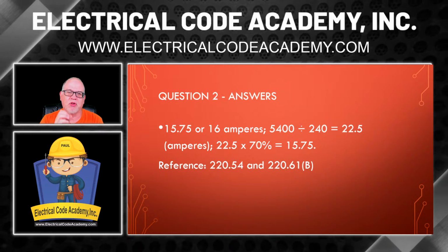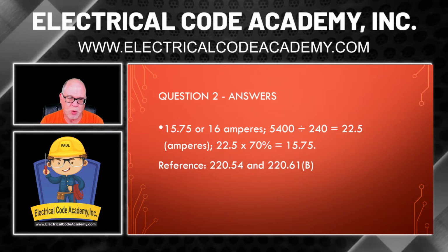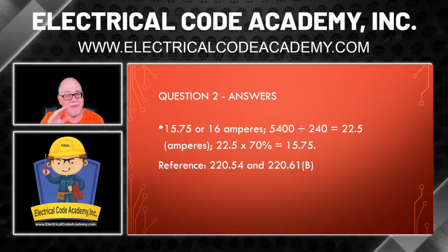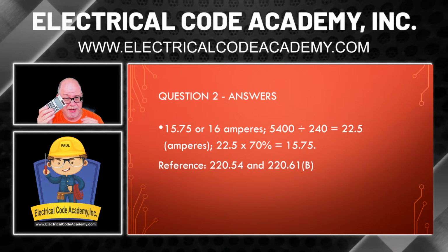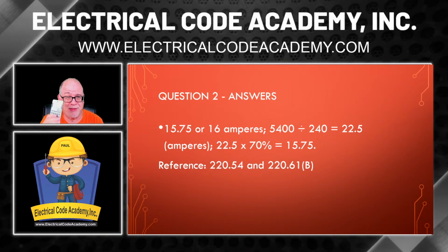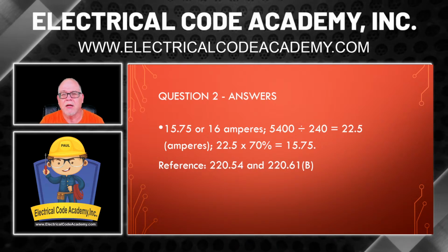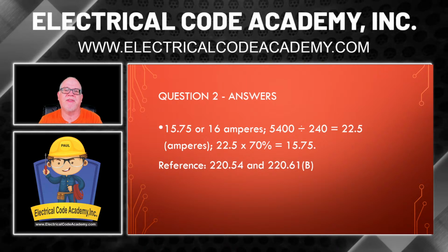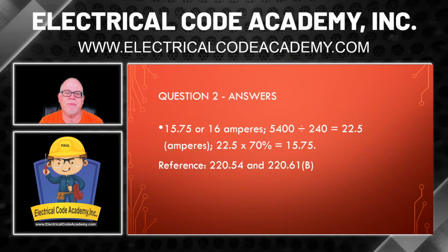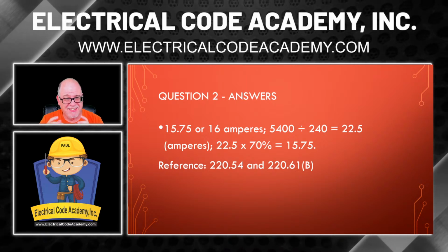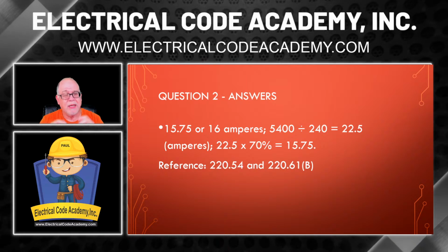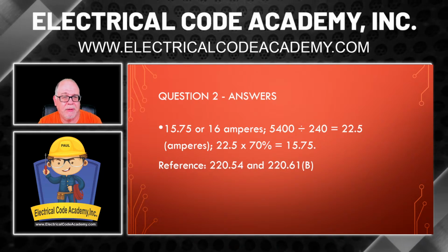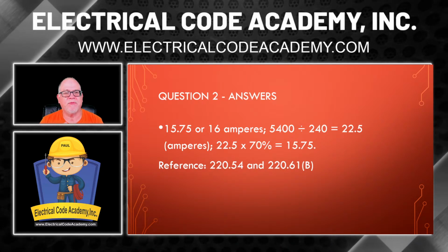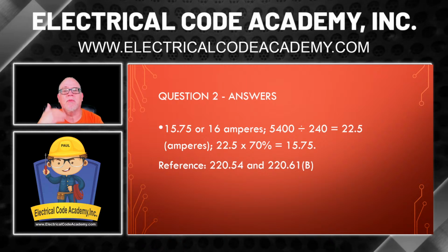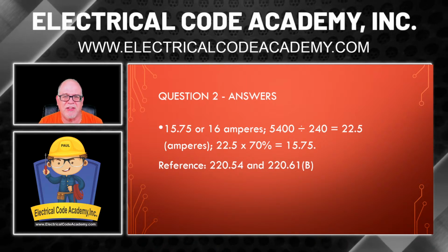And that means you're working with decimal values. Of course, you've got a calculator, probably doesn't matter, but what if that calculator went dead? So much easier to work decimals with decimals, right? Anyway, so 22.5 times 70% is 15.75, and that is the actual contribution. Now, since we're dealing with amps, the code does allow you, if it's 0.5 or greater in amps, to round it up to the next available size and use that.